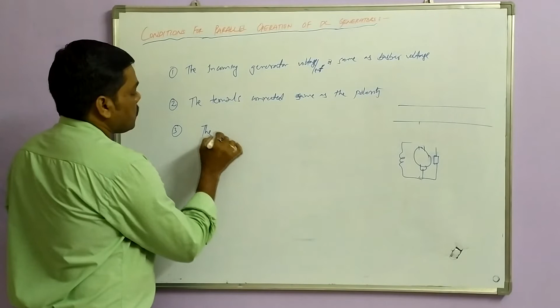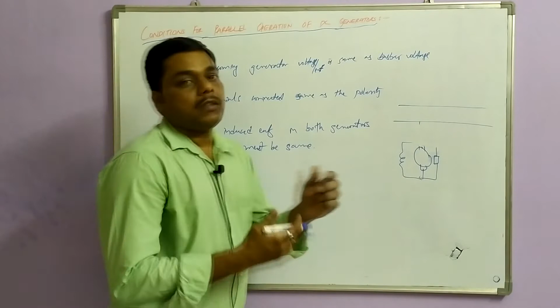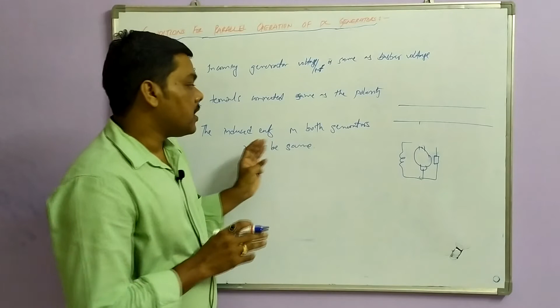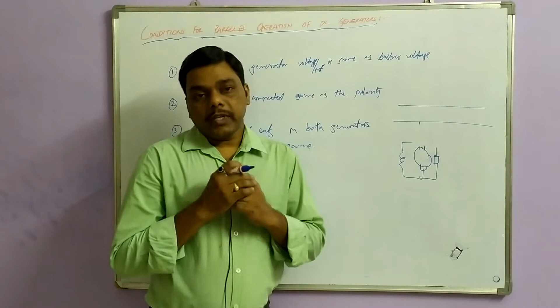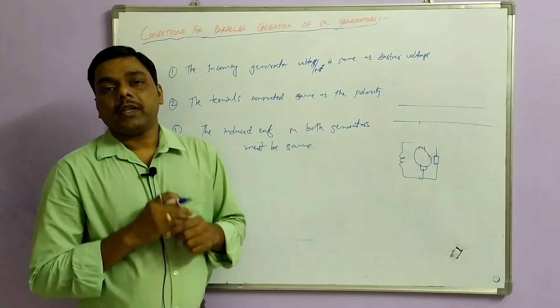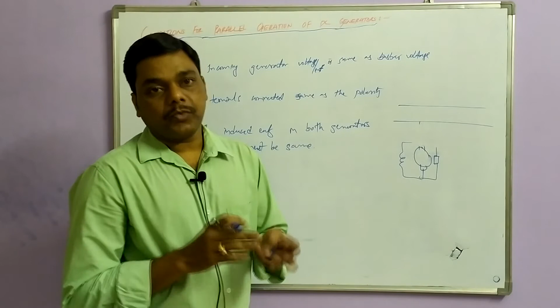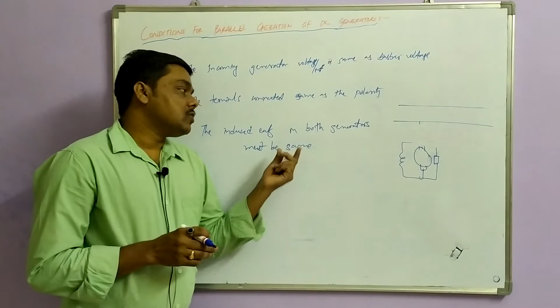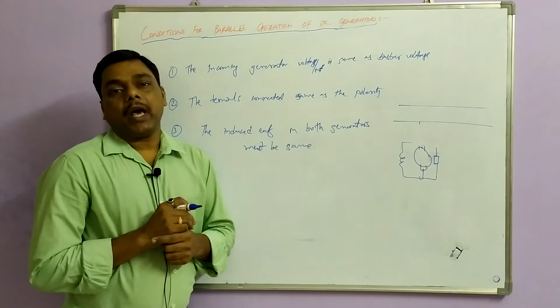The third one is that the induced EMF in both generators must be the same. According to their voltage drop and the rating of the generators, they must induce approximately the same voltage. If this condition is met, the parallel operation will be very good. The generators' induced EMF depends on their armature drop, series drop, and also for compound generators, so the induced EMF should be the same, then it will easily go for parallel operation.